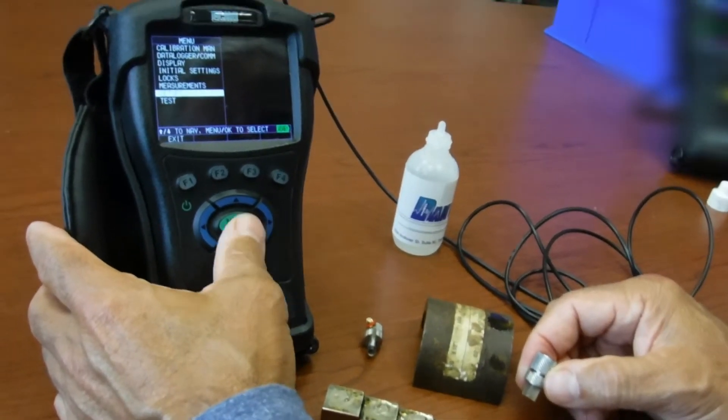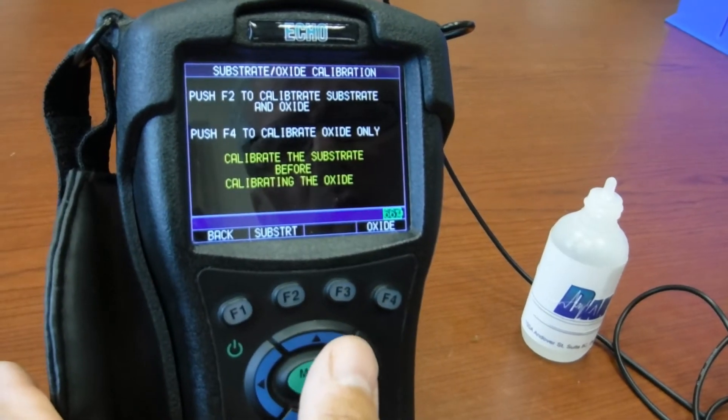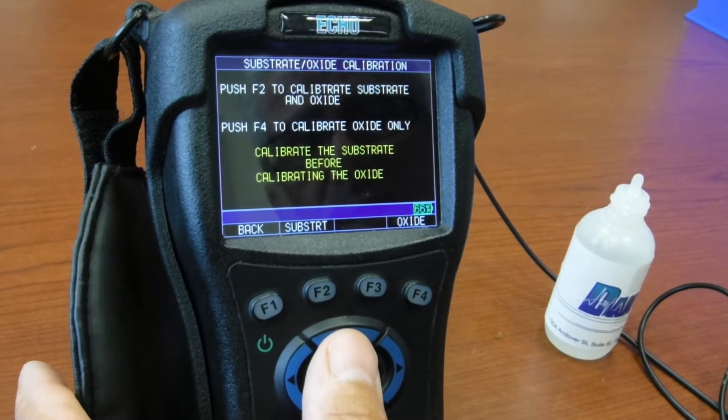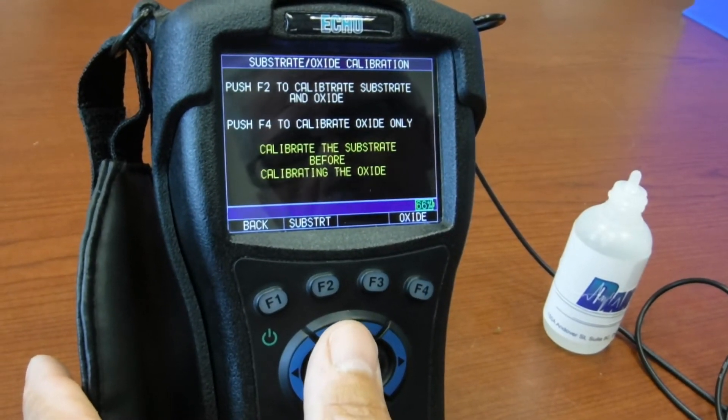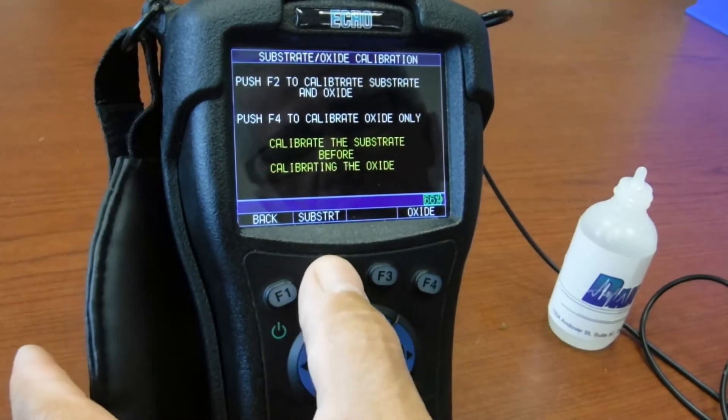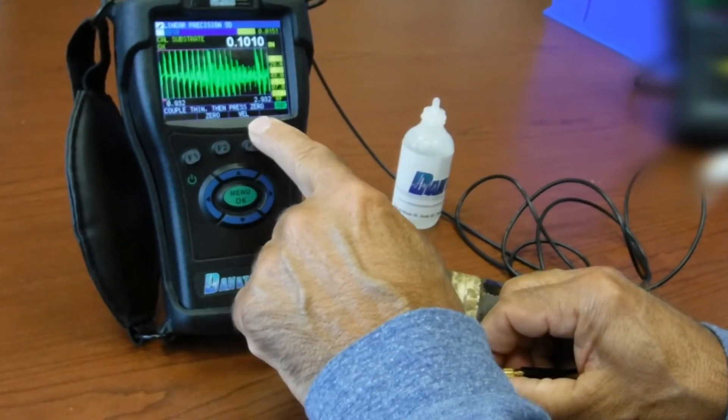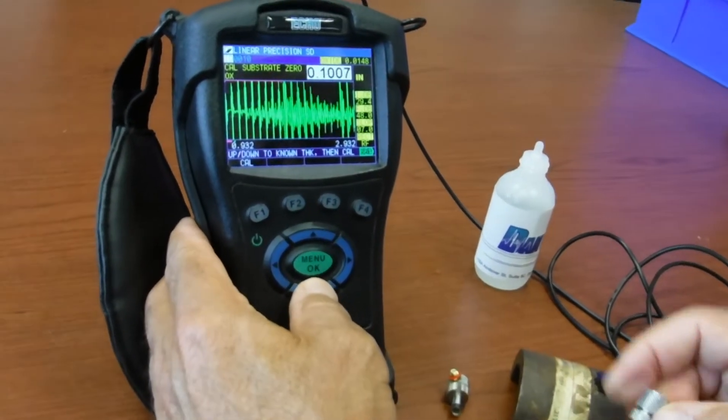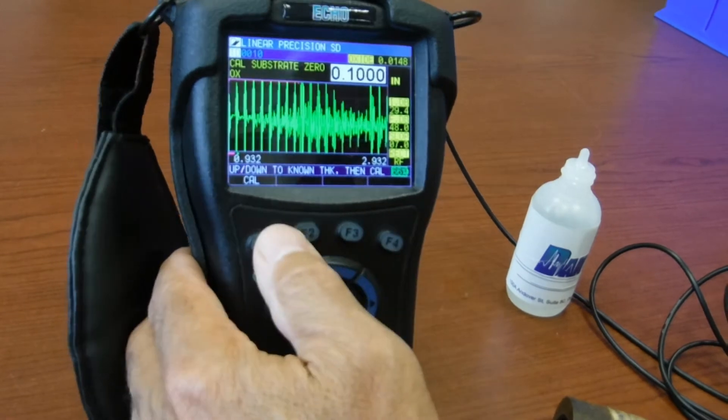I press menu OK. I scroll up to calibration manual. Note that you can only operate the calibration in manual mode. The automatic calibration feature does not work in the oxide scale mode. I press F2 for substrate as the prompt says. Coupled to one hundred thousandths. Press zero which is above F2. Scroll down to the known thickness and then press CAL as the prompt says.